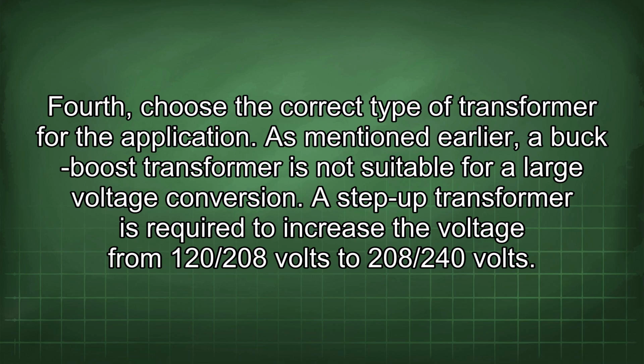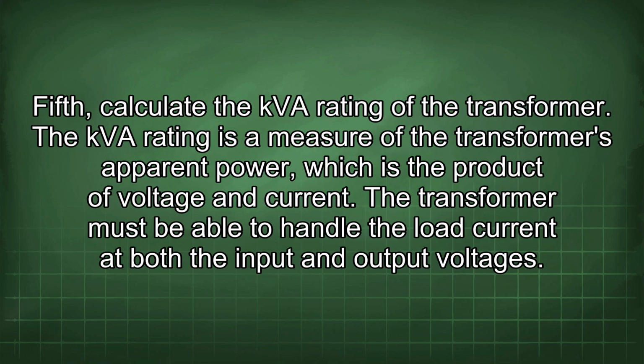As mentioned earlier, a buck-boost transformer is not suitable for a large voltage conversion. A step-up transformer is required to increase the voltage from 120/208 volts to 208/240 volts. Fifth, calculate the kVA rating of the transformer. The kVA rating is a measure of the transformer's apparent power, which is the product of voltage and current. The transformer must be able to handle the load current at both the input and output voltages.